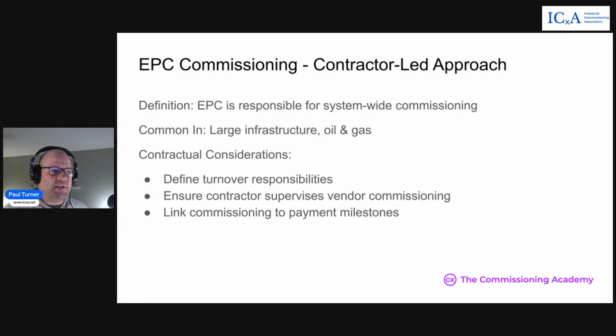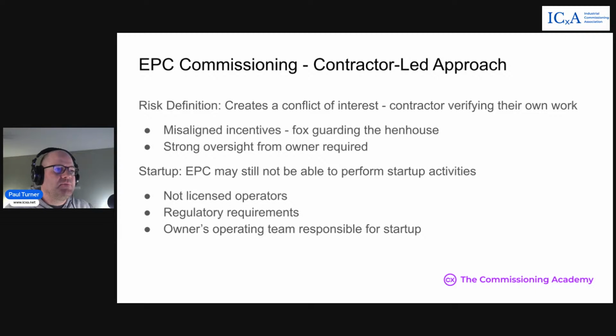In a lot of cases the EPC is responsible for procurement of equipment, so vendor involvement for equipment startups needs to integrate into the contractor's activities. Because of the conflict of interest created here, it's very important to link commissioning to payment milestones, to make sure successful gates within the commissioning process are achieved and tied to payments, so the owner gets the quality systems they're expecting.